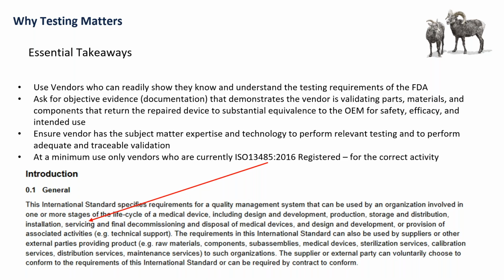At a minimum, use only vendors who are currently 13485:2016 registered for the correct activity, and that's important. So you've probably all seen what the certificate looks like, but what you want is for them to send you a copy of that certificate, and you say, I'm going to be sending this company probes for repair, for example. So make sure you don't just look and say, oh yeah, they're 13485, but that's not a halo to repair everything. It has a scope right above it that actually defines what this certificate is good for. And it says just design and development of processes, technologies, fixtures, and tools used in the repair and refurbishment of diagnostic imaging probes. Okay, very, very specific.